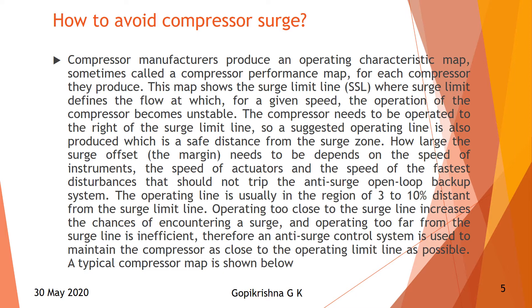Compressor manufacturers produce an operating characteristics map, sometimes called a compressor performance map. Each compressor manufacturer will give a performance curve for each compressor, at which particular limit you will get maximum performance if you maintain all parameters correctly. The surge limit defines the flow at which, for a certain speed, the operation of the compressor becomes unstable. The compressor needs to be operated to the right of the surge limit line. A suggested operating line is also produced which is a safe distance from the surge zone.